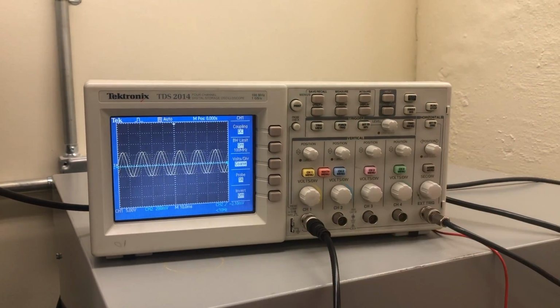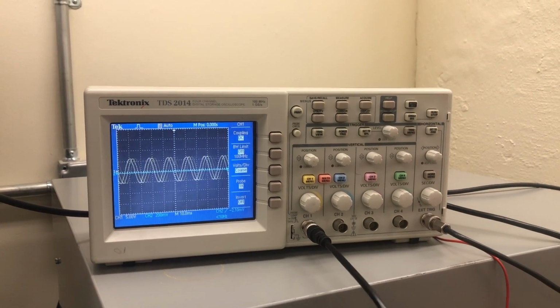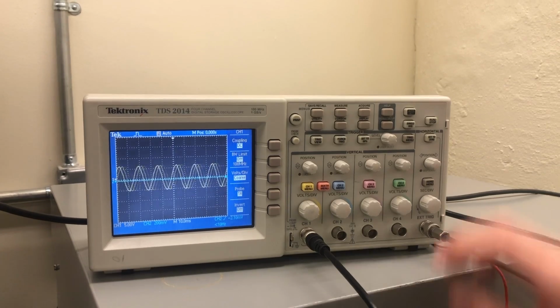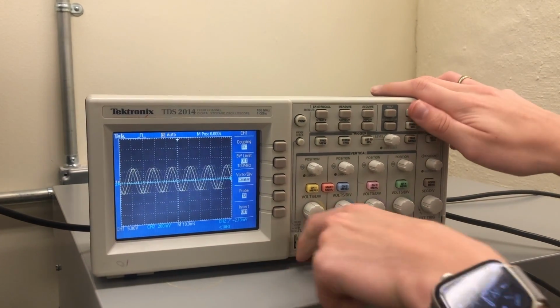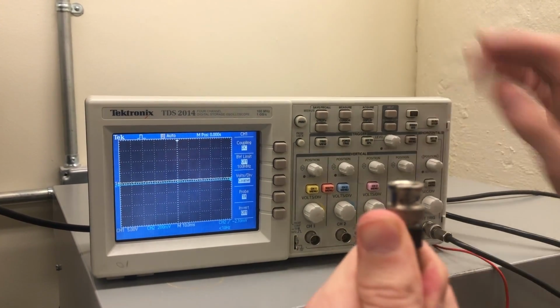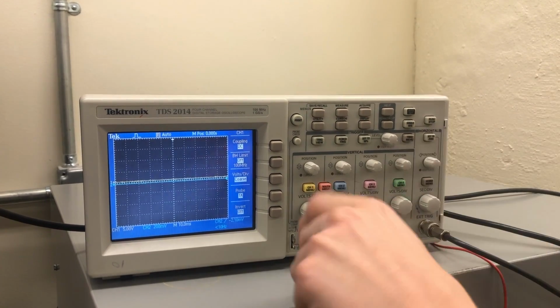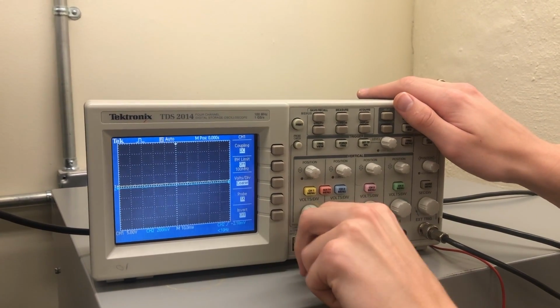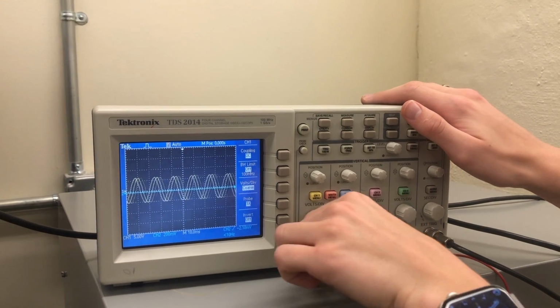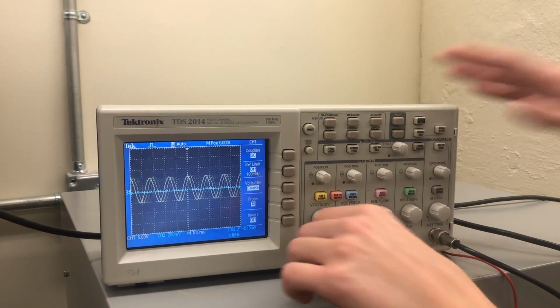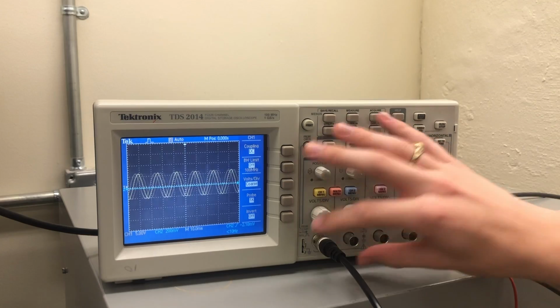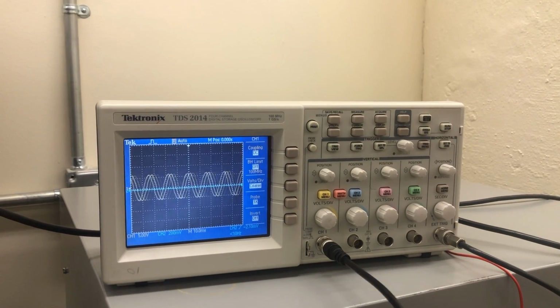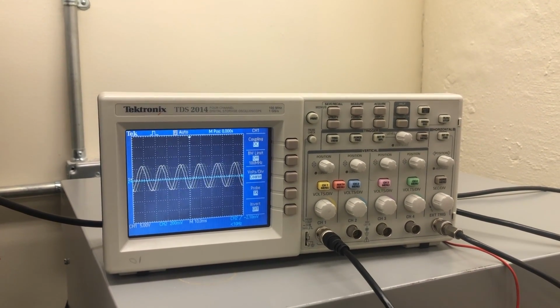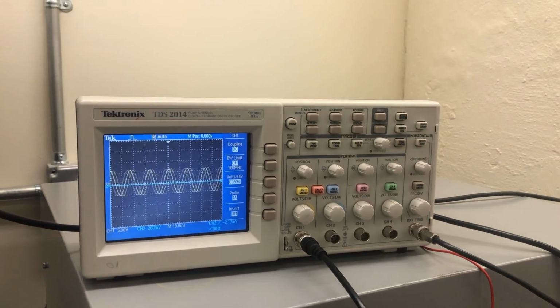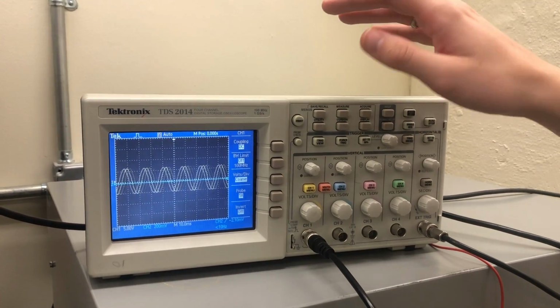Your probe right now is at 1x. Always be sure that it's 1x. These BNC cables that plug into this, this is a BNC cable here, must be set as a 1x probe scale. Most normal probes that you plug into an oscilloscope are 10x probes. These are 1x, so be very careful about that. Otherwise, the measurements you're getting off of here are wrong.